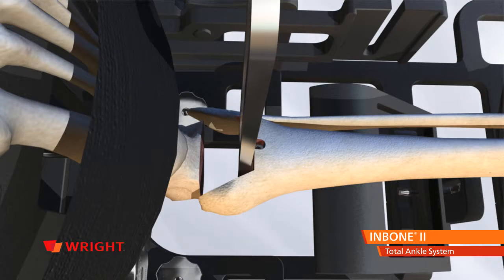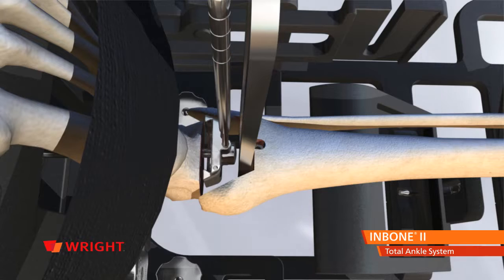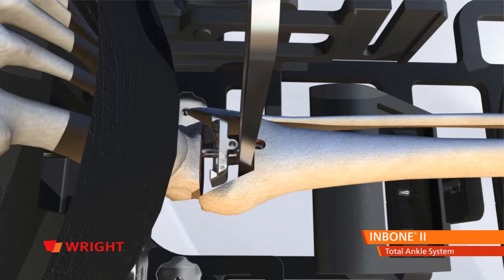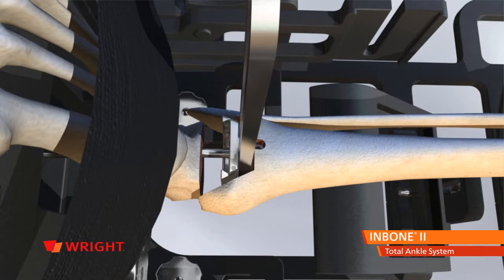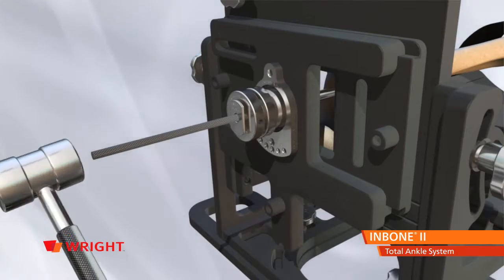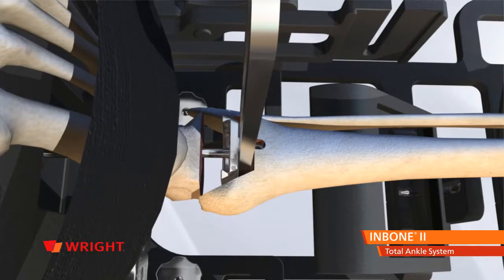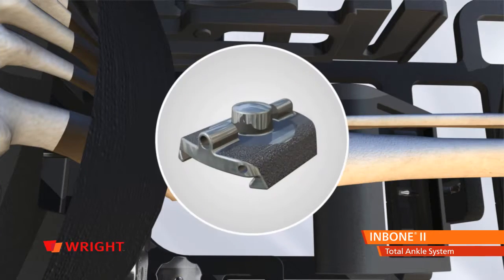Holding the tibial stem base with the wrench, introduce the tibial tray using a holding tool. Insert the Morse taper on the tibial tray into the stem base. Remove the holding tool before striking the strike rod. Push the strike rod into the indentation on the bottom surface of the tibial tray. Holding the stem base firmly, strike the end of the strike rod with a mallet to seat the Morse taper.